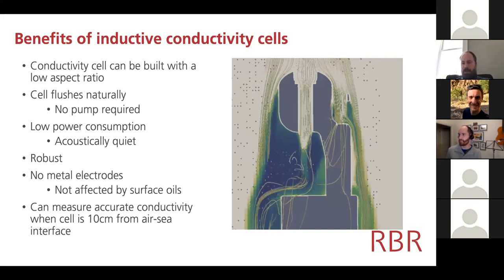In an RBR cell, we are not sensitive to microscopic amounts of fouling, whether that's a physical contaminant or a biological contaminant. Once that contaminant starts to have a significant geometric impact, then absolutely the RBR cell appears to be fouled. And it's not because it's not able to measure conductance or resistance correctly. It's doing that correctly all the time. But it is this conversion using the cell constant from conductance to conductivity that is no longer holding true, because that's really a geometric concern.